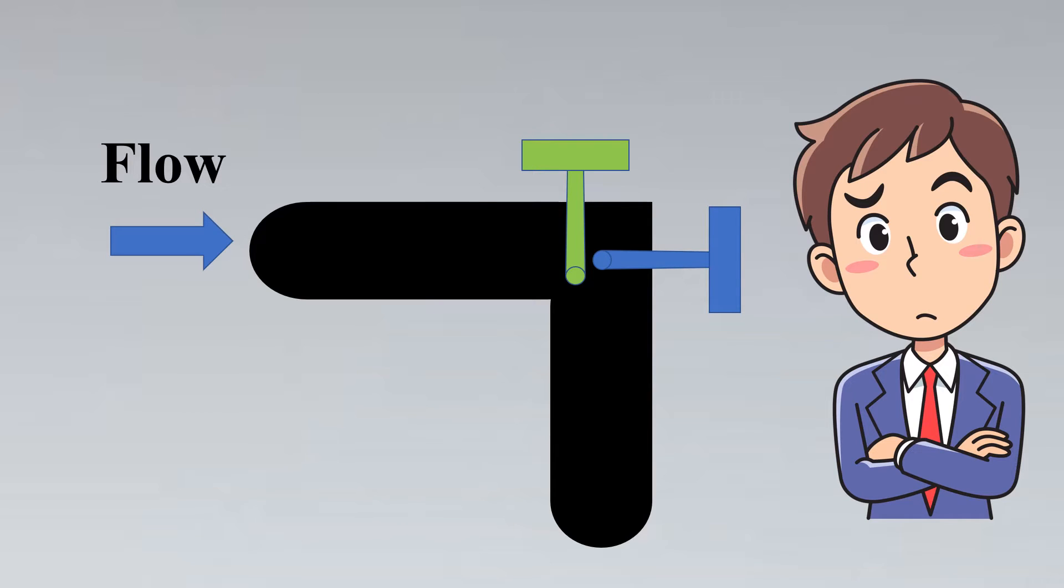You might wonder that does it even have any effect on the thermowell? It has an extremely high effect on the thermowell. Let's look as to what the international standards have to say about such an installation. The most well-renowned recognized standard for thermowells is ASME PTC 19.3. This is widely accepted standard throughout the world.